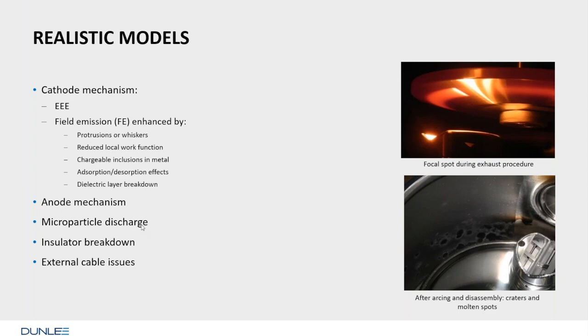Another number 3 effect may be microparticles. So we will see in a minute how that works. Microparticles may bounce back and forth between anode and cathode, and they may also create little discharges because they bring charge, and if they approach a surface, they may trigger discharges, which then in turn release lots of energy, such that a big discharge may occur. This is a rare event, but it happens. I think it happens predominantly if these microparticles are charged and dielectric and not metal, but well chargeable, like metal ceramics dust or glass dust or whatever. But it can also be that metal particles do it. And then we have insulator breakdown and, of course, external cable issues.